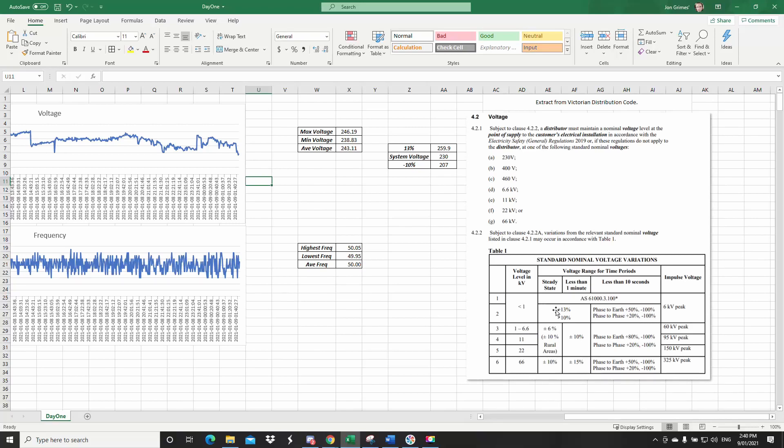So if we're just looking at this steady state voltage, so plus 13%, minus 10%. So if our system voltage is 230, then our ceiling 13% would be 259.9, and a sag of 207 volts.